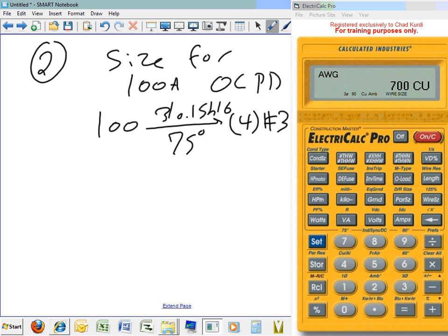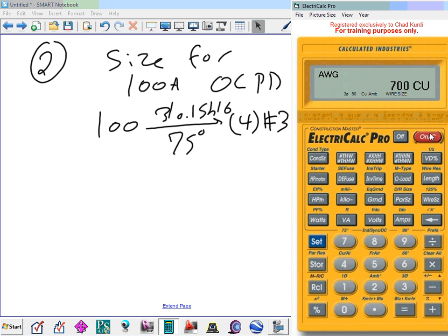Can I verify this one, guys, quick with the calculator? The first thing to verify with the calculator, remember my calculator is already screwed up here, so clean. I need to go reset my calculator to 75. Why 75? I reset my calculator to 75, so basically size everything now based on 75. The first one was 50 amp, wasn't it? 50 amp, hit 50, put your amp, and find the wire size.